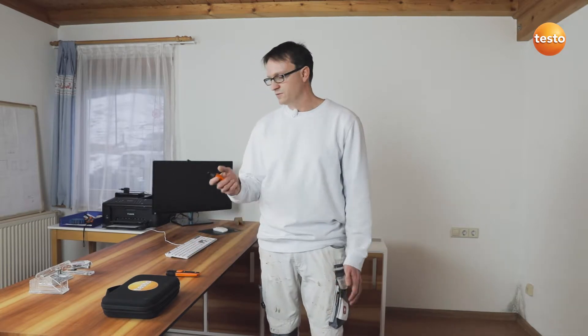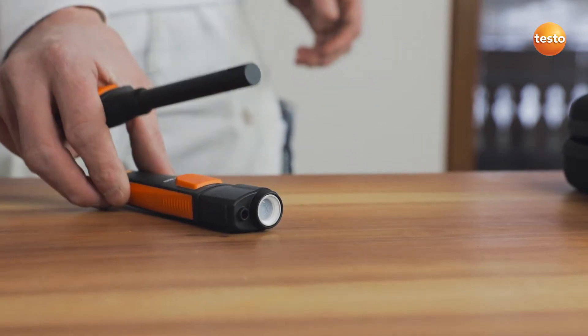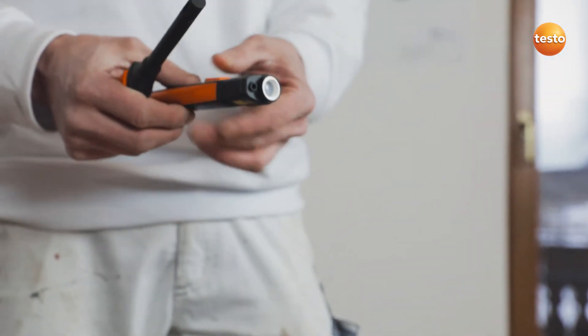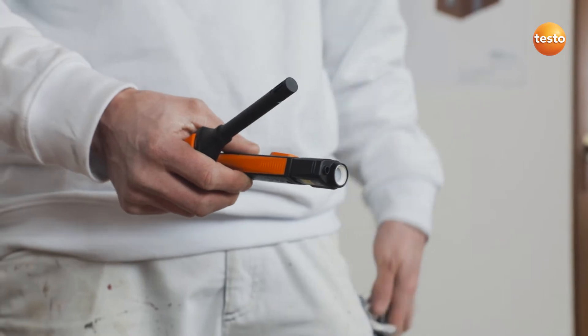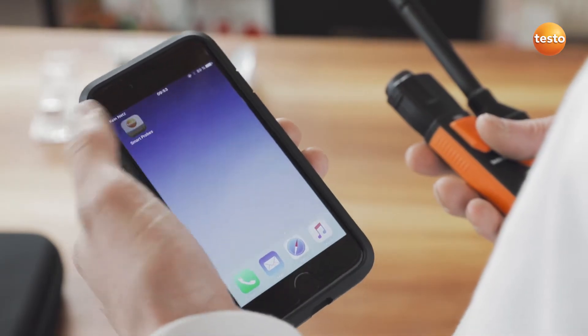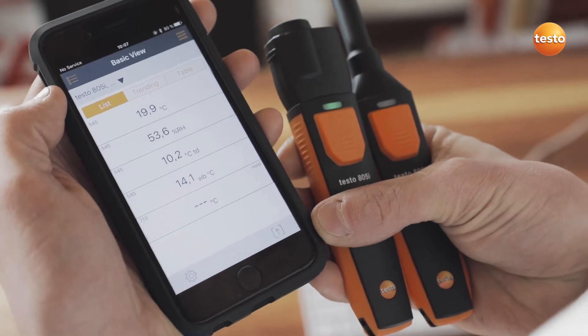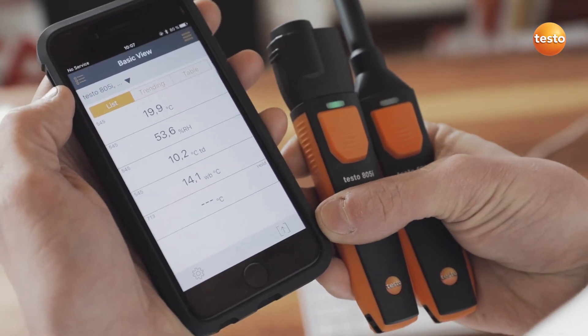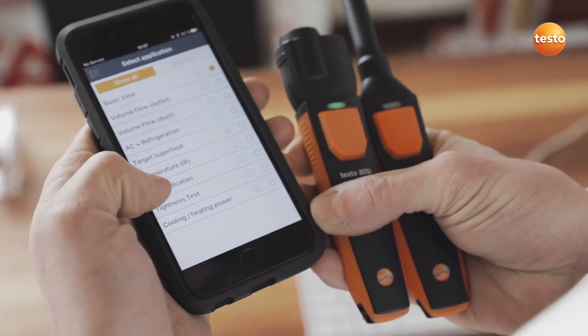I'm switching on the Testo 605i now. It measures the room temperature and the humidity. I switch on the infrared thermometer Testo 805i and open the Testo Smart Probes app. Both smart probes are now connected and are flashing green. I select mold indication in the app menu.